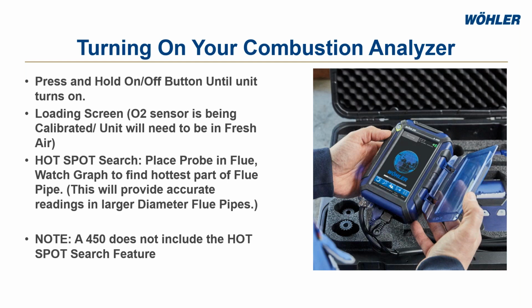If you have an A550, you're going to notice that your startup's a little bit different. On your startup, the first thing you're going to see is a hotspot search. What the hotspot search is, I call it kind of a metal detector. It's looking for the hottest part of your flue. So if you're testing boilers with big diameter flues, you want to make sure that you're finding the hottest point of that flue. We'll get into a little more of the hotspot search and how to use that.